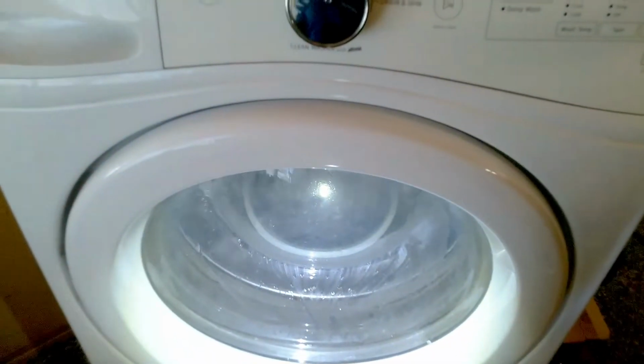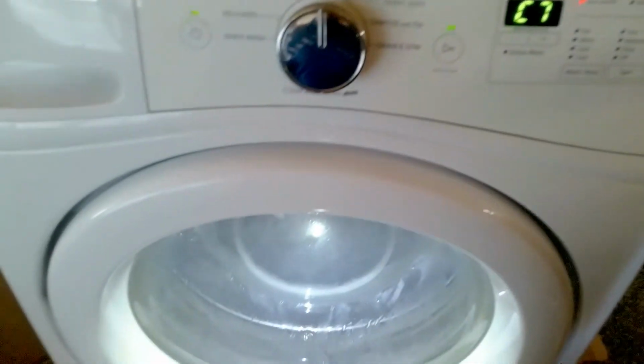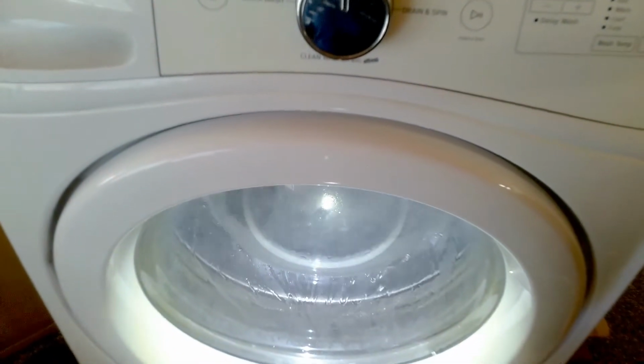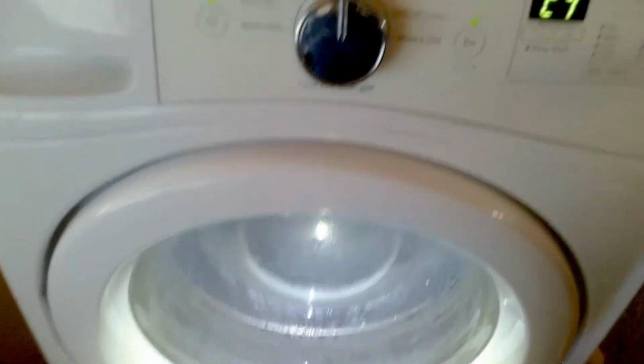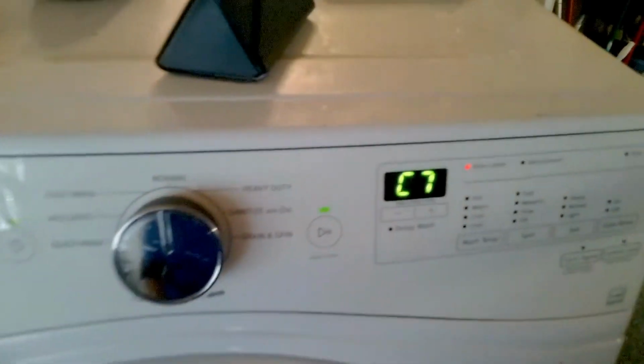Okay, test mode C7. This will activate the drain pump. Should be 15 seconds. So basically test the drain pump and the water level sensor. So as we saw at the beginning of the video, we got the error code that meant water level sensor, but most of the time it's actually the drain pump, and this is why.